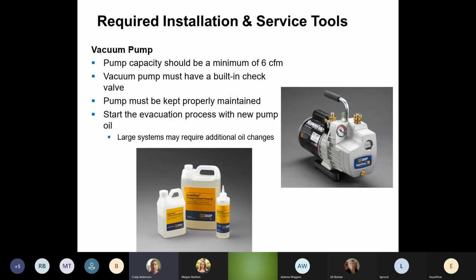Let's make sure we have a built-in check valve in our vacuum pump in case that vacuum pump turns off when we're doing a vacuum. Your system's going to be in a negative pressure. So if your vacuum pump doesn't have a check valve and it turns off, we can actually pull liquids from that vacuum pump into our system. So we want to make sure that we have a built-in check valve and the vacuum pump is operating properly.